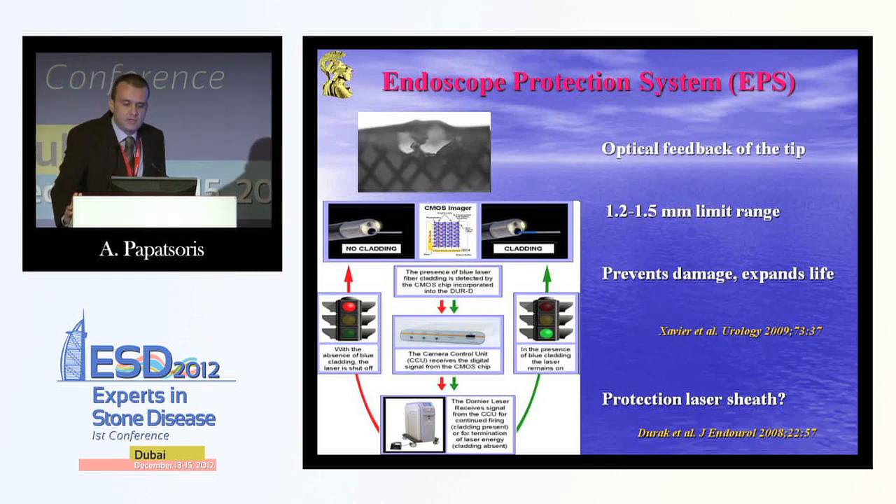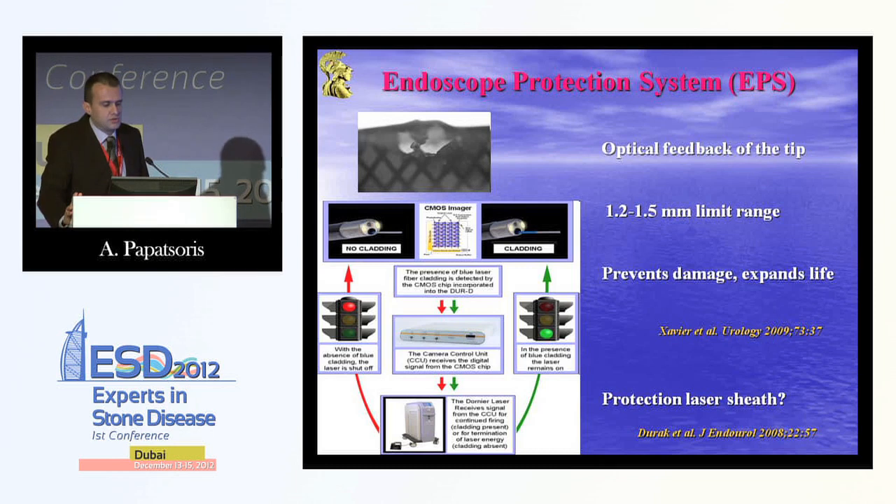Many colleagues will be afraid that by using a laser inside a flexiscope, they'll damage the very expensive scope. But technology has progressed even in this aspect — for example, for the Gyrus ACMI digital scope, the endoscope protection system has a sensor on the tip of the scope that detects whether there is cladding or not. If there is no cladding, you are unable to fire the laser, which is very important because it prevents damage to an expensive scope.